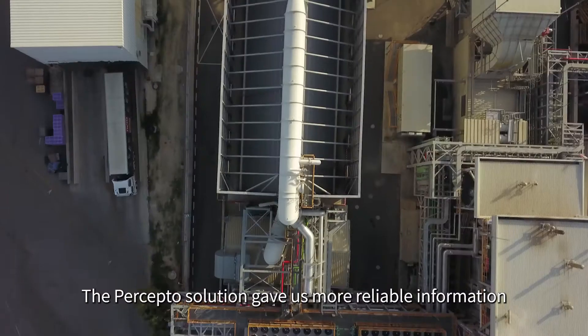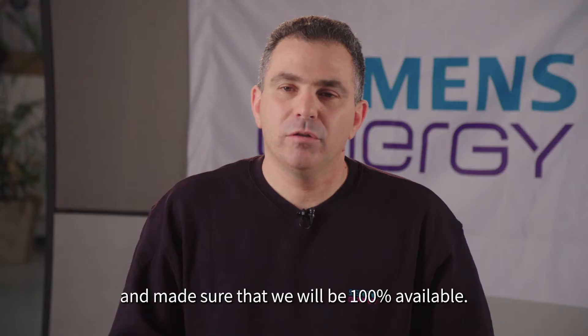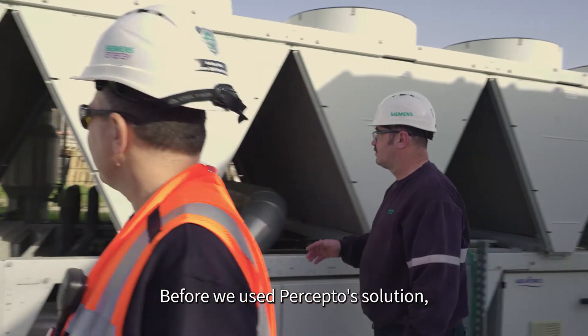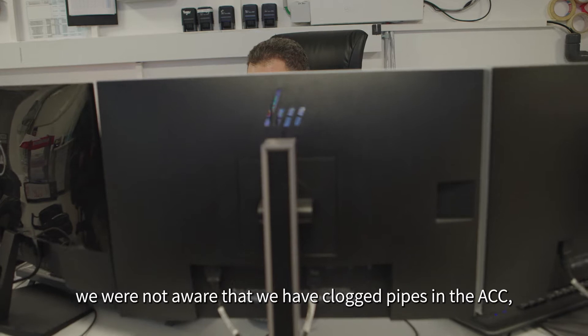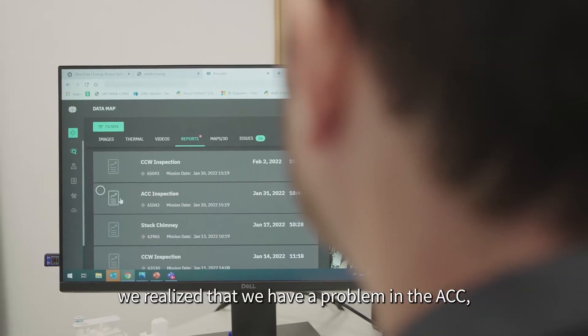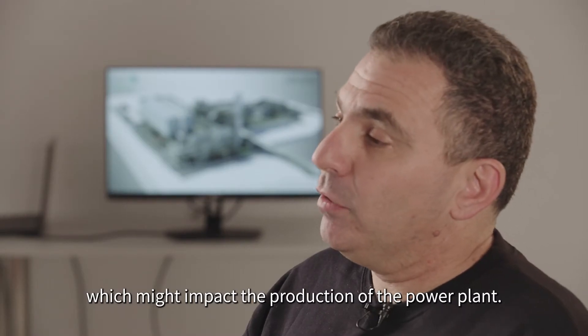The Percepto solution gave us more reliable information on the power plant production and makes sure that we will be 100% available. Before we used the Percepto solution, we were not aware that we had clogged pipes in the ACC. With the reports we received from Percepto, we realized that we have a problem in the ACC which might impact the production of the power plant.